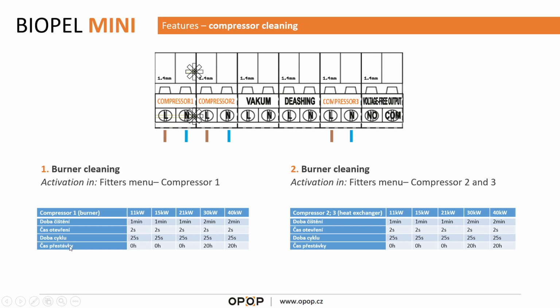The last function is cleaning delay or cleaning interval, let's say. Usually it's 0 hours, which means that the cleaning will be performed only during the extinguish phase of the boiler, not during operation. If you activate the cleaning interval and you select here, for example, 20 hours, as you can see for the bigger power, there is 20 hours pre-selected from the factory, and that means that each 20 hours of operation the boiler will switch off and the burner cleaning will be performed also during operation. The reason for that is that, of course, with bigger boilers, with bigger burners, you create more ashes, and the ashes should be cleaned more often.